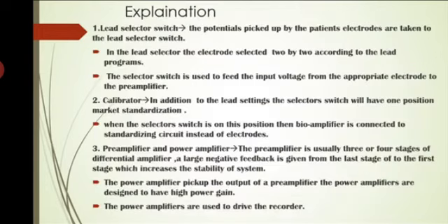First, lead selector switch. The potential picked up by the patient electrodes is taken to the lead selector switch. In the lead selector, the electrodes are selected two by two according to the lead programs. The selector switch is used to feed the input voltage from the appropriate electrode to the preamplifier.